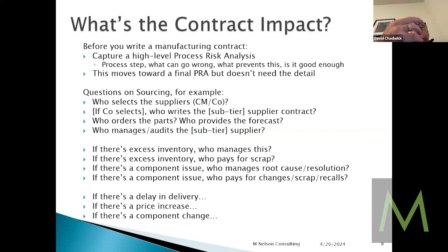So you don't go off the shelf. I mean, you can if you don't have any tighter specifications. In my experience, I would order screws, or somebody would order screws or silicone material or something, and we would tell the supplier, this is our specification. Whatever Luke or somebody said earlier, 10 megahertz, and he was working at 7.5, we wouldn't have accepted the off-the-shelf product to put into a medical device. We might have taken it to put into plumbing supplies or computers if we were builders of those, but not in the medical world, having to follow the quality system regulation. Evaluating suppliers, contractors, and consultants.